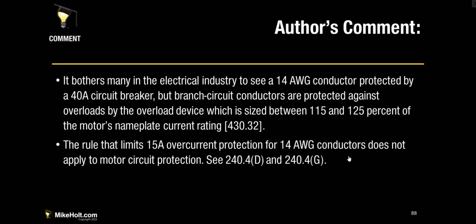Oh, I want to go back to that slide. It bothers many in the electrical industry, this is kind of funny, to see a 14 AWG conductor protected by a 40 amp circuit breaker. You see what he's talking about? But branch circuit conductors are protected against overloads by the overload device, which is sized between 115 and 125% of the motor's nameplate current rating. The rule that limits 15 amp overcurrent protection for 14 AWG conductors does not apply to motor circuit protection.